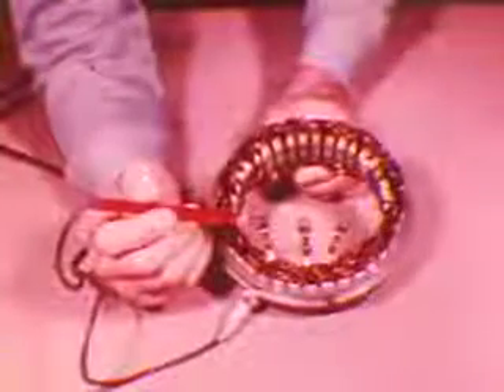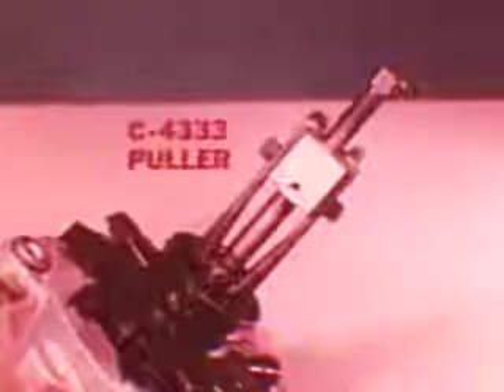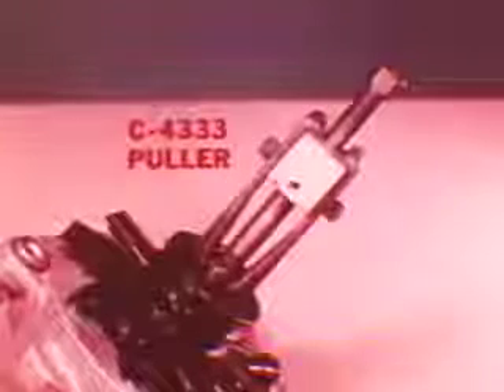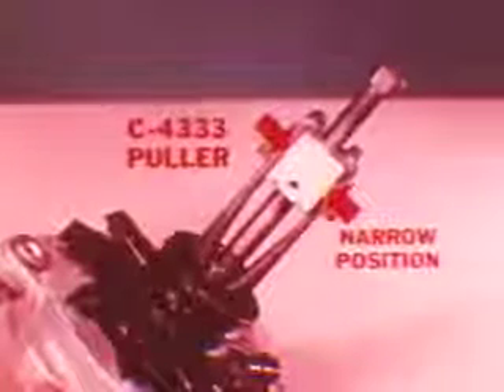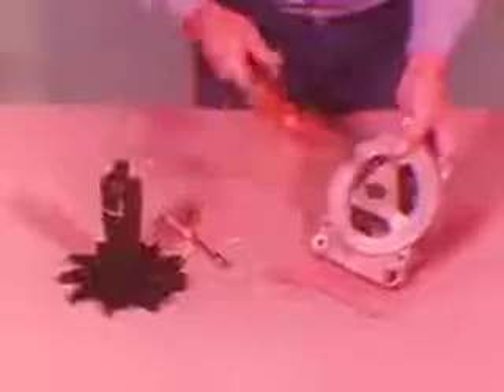Further procedures for checking rectifier diodes and for testing stator windings, the rotor field coil, and other components are described in the service manual, so we'll omit them here. The drive pulley and bearing are removed with the same puller tool. For pulley removal, the spacer block of the puller is placed in its narrow position. With the pulley off the shaft, remove the bearing retainer screws and tap the drive end of the rotor shaft to separate the bearing and rotor assembly from the end shield.